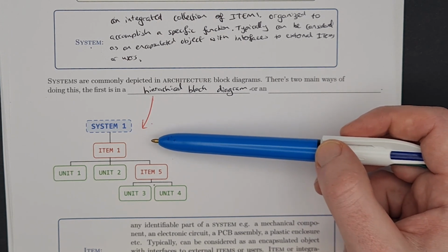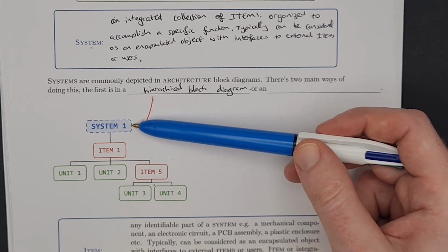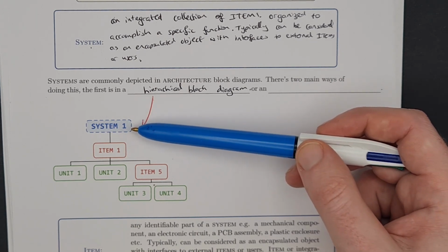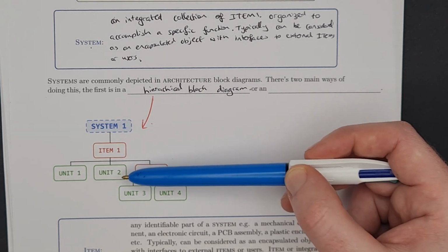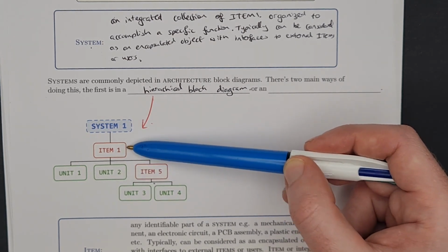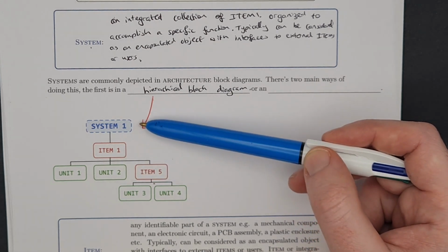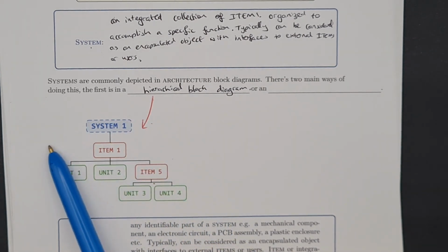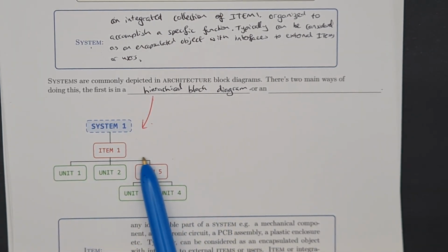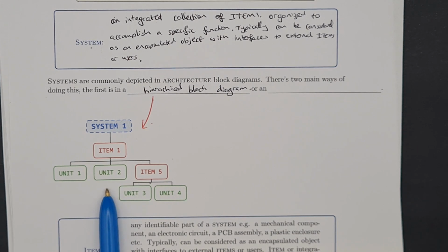And the general rule of thumb is hardware is tested only at the system level, but software is tested at the system, item, and unit level. Sometimes people won't test at the unit level. They'll do static code analysis and then just test at the item and system level. So that's mainly what we're indicating here. And we're just trying to decompose the system into testable blocks. And it's always going to be setting a higher level of testing that really, at the end of the day, is making devices more safe and effective. And that is why this decomposition happens.